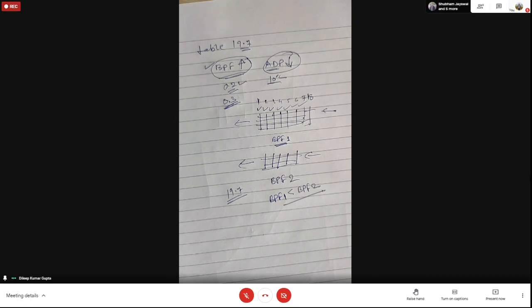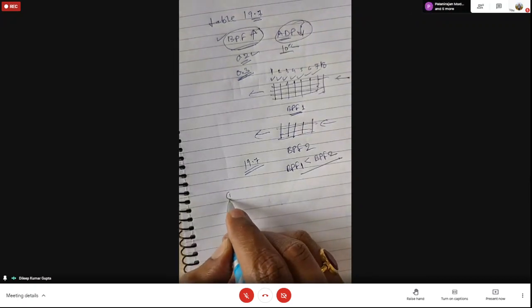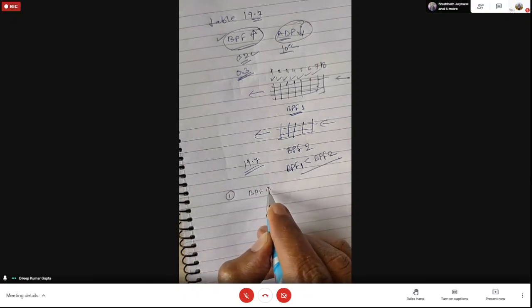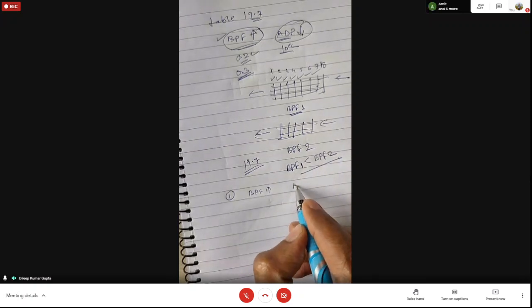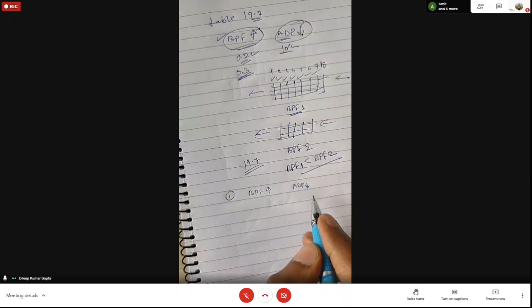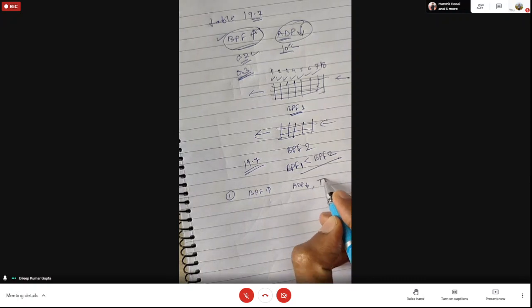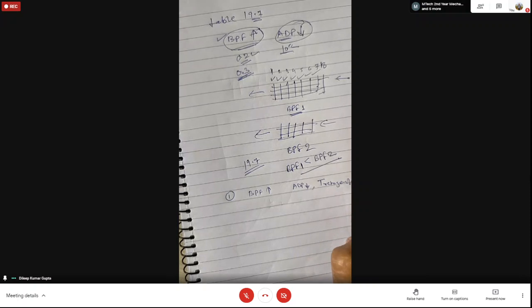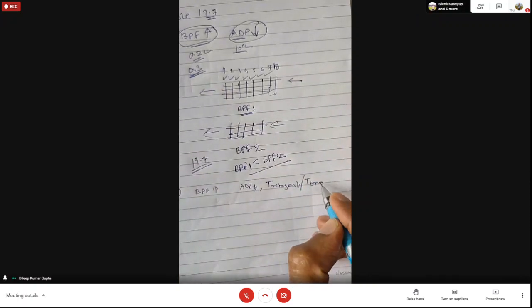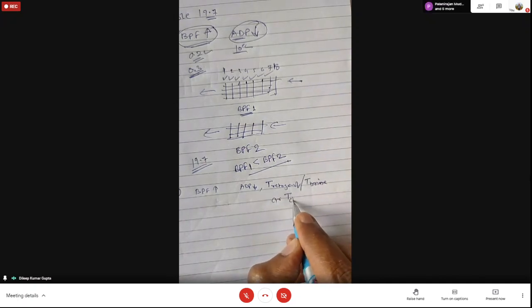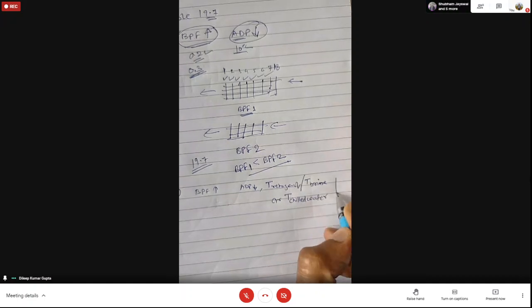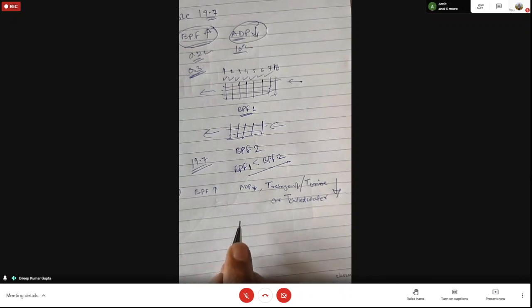for the whole system. So it is desirable to have a low value of bypass factor and a high value of apparatus dew point, but we also have to think about that, for a particular application, how much we should use and up to what range we should go. Right? So let us summarize what we discussed. What happens if the bypass factor is higher? See the effect. The effect is the ADP will be low, then the required T refrigerant or T brine will be lower, T brine or chilled water, the temperature of chilled water will be lower. If it is so, then what will be the consequence?